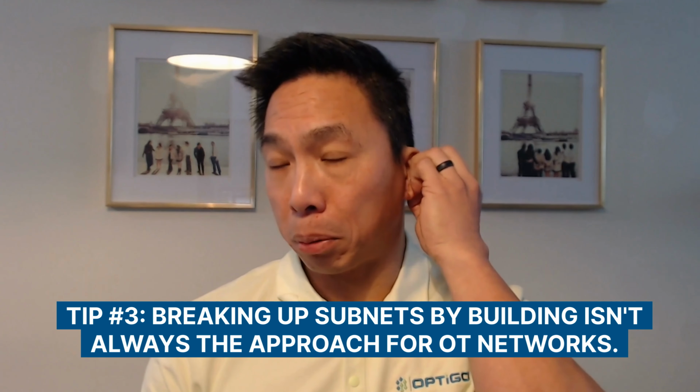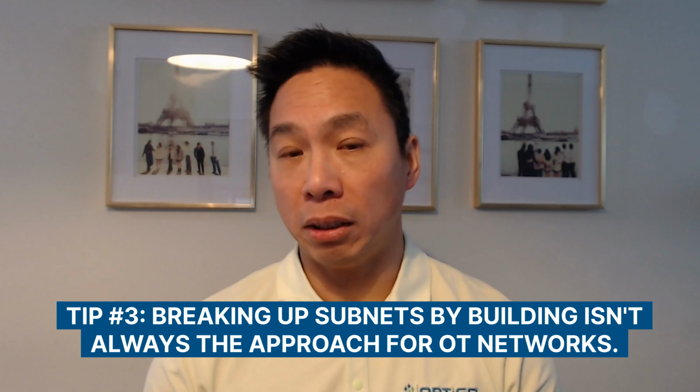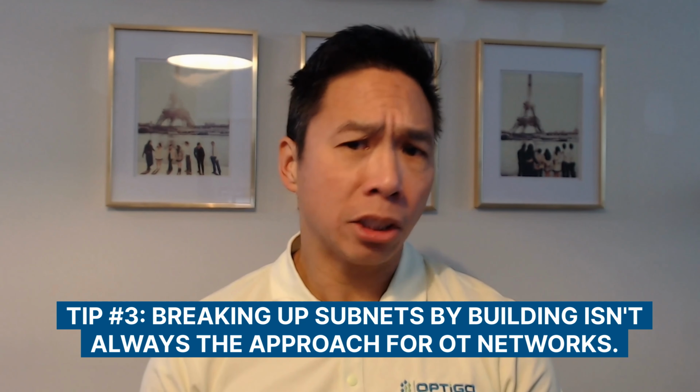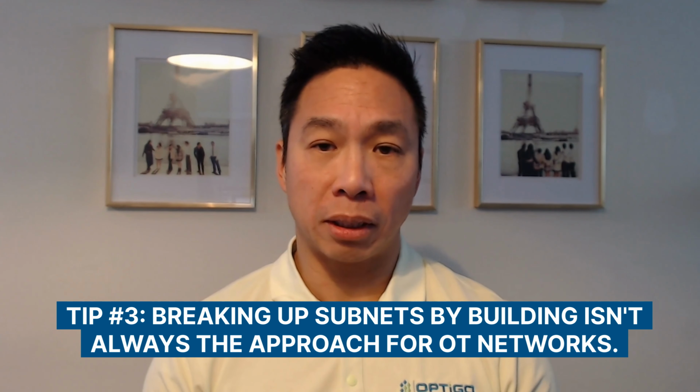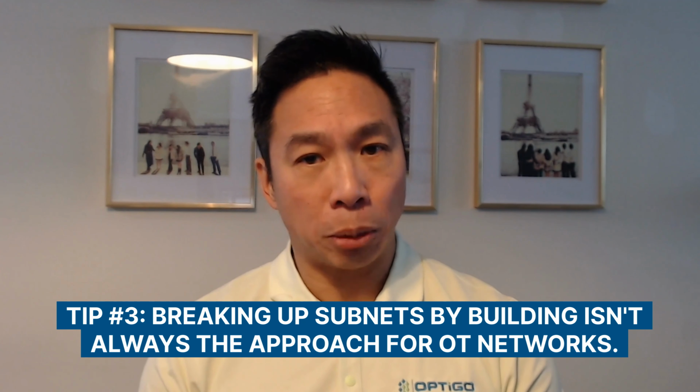On that note, I will mention one common approach is to break up per building, a subnet per building. It is not always adequate for building systems. In general, it is pretty good, but just keep in mind that a central plant does need to talk to everything. Therefore, that central plant needs to route to and from every building. So explain that to your IT experts. They may be able to provide a better approach. They may also be able to provide a routing method that is optimal for this case.